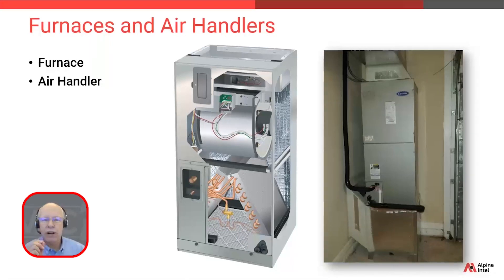Here's a photo showing an actual air handler, installed in what looks like a garage. Without opening the panels, it's sometimes hard to tell what you're looking at. But let's use what we just learned — there are a few clues. In this photo, there's no gas line and no exhaust flue. The refrigerant lines are entering the lower compartment, telling us the evaporator coil is in the lower compartment, which is indicative of an air handler only. Also note that silver box at the very bottom — that's not actually part of the ductwork; that's known as the plenum, and we'll cover that in more detail shortly.